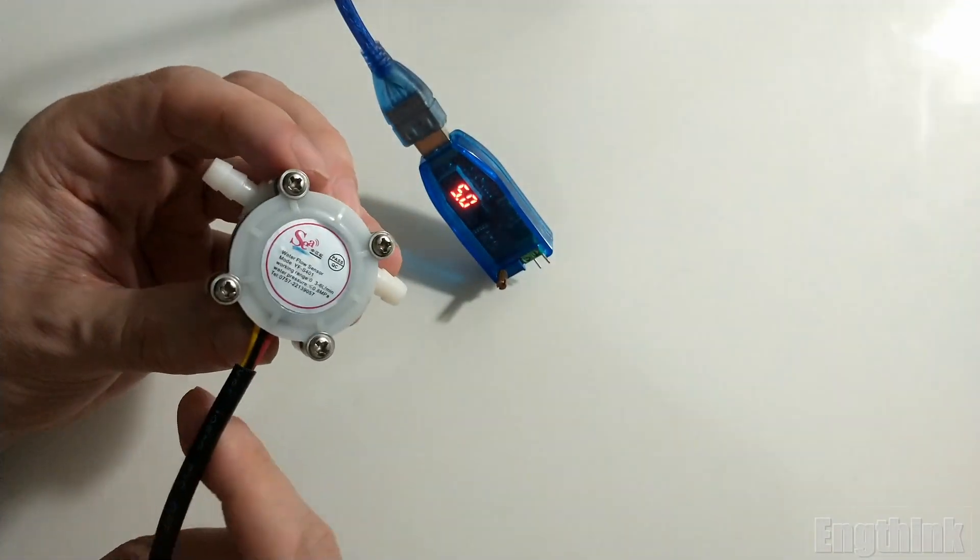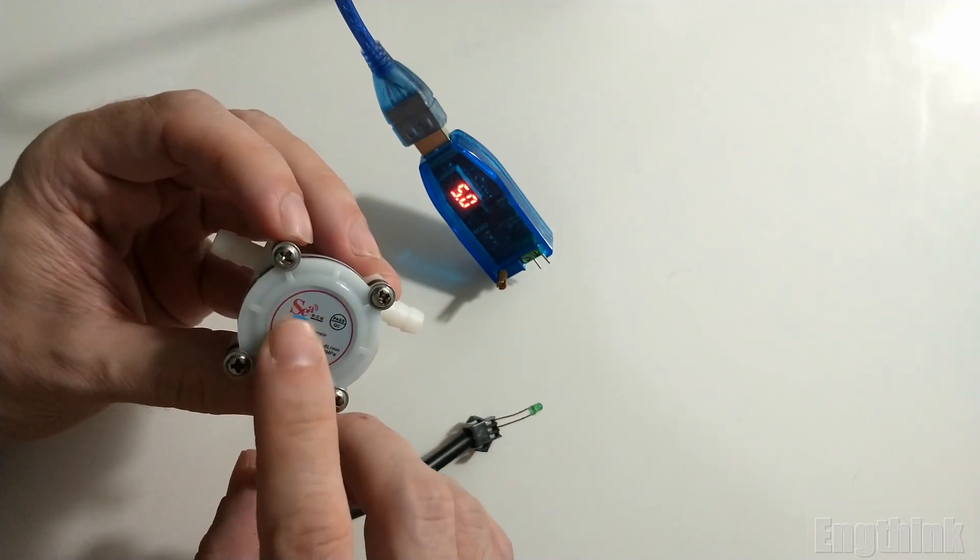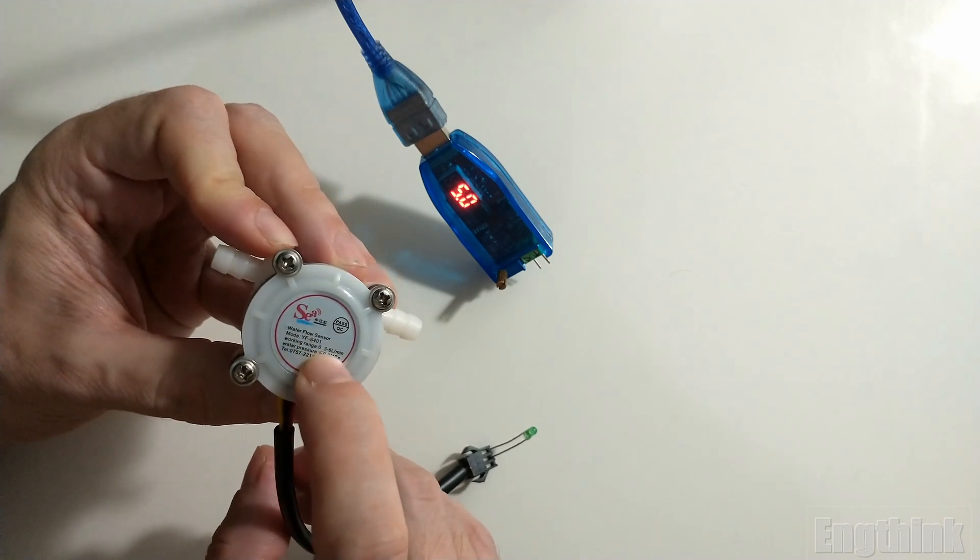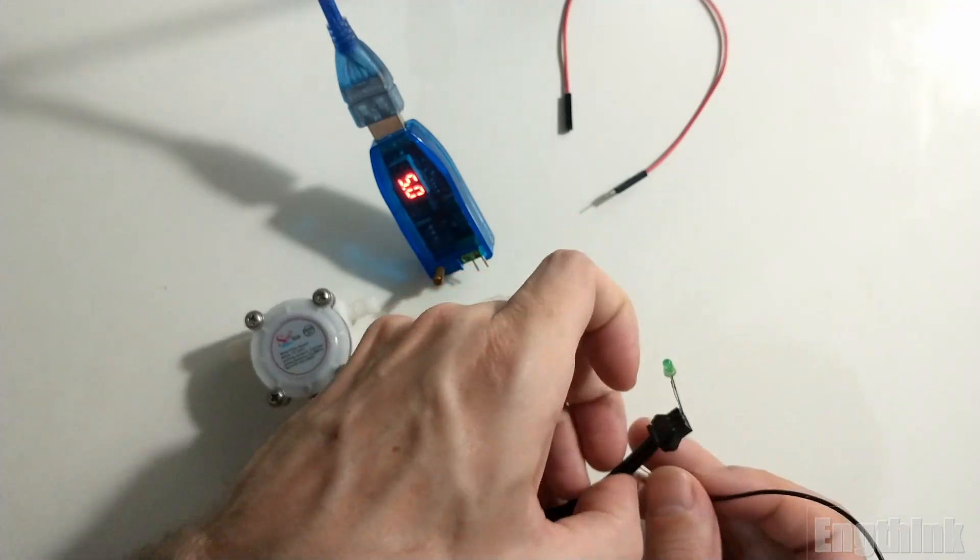Connecting the DC/DC converter, let's adjust it to 5 volts DC. I want to emphasize that the voltage range is on the label of the flow sensor. As we can see, it's between 4.5 and 24 volts DC.